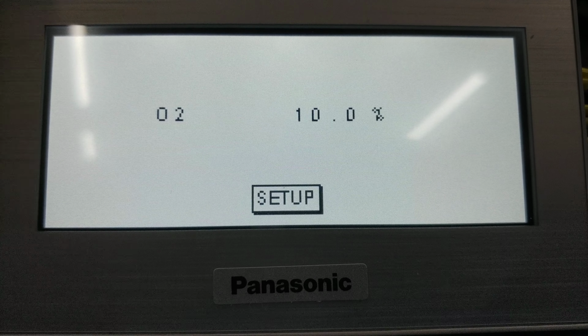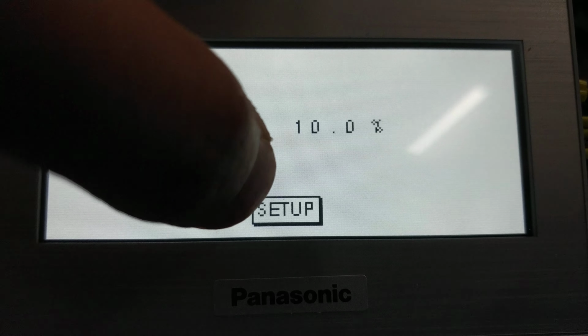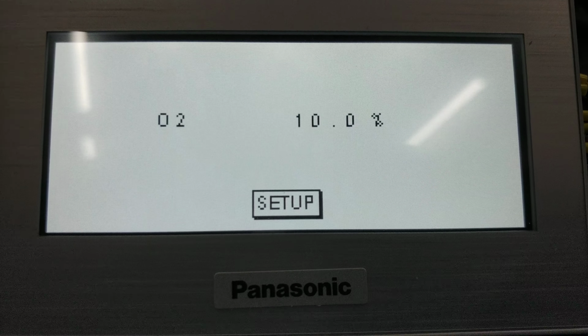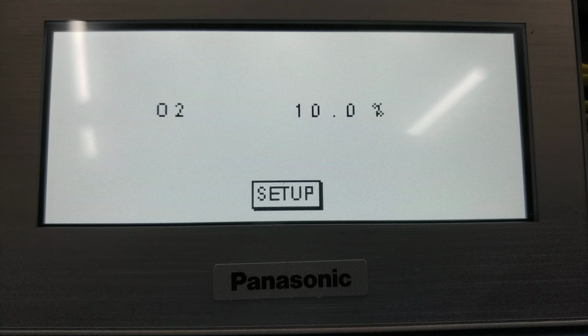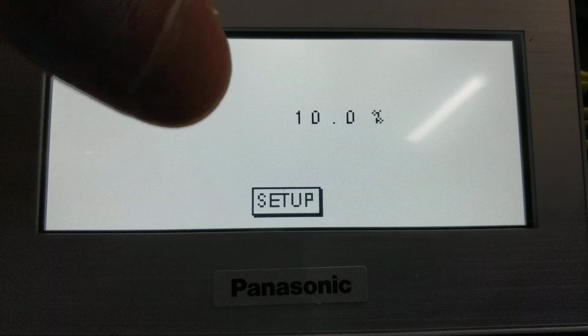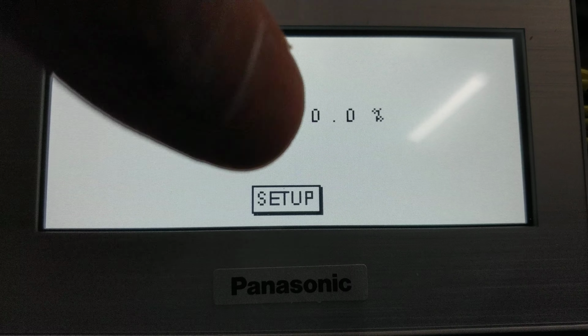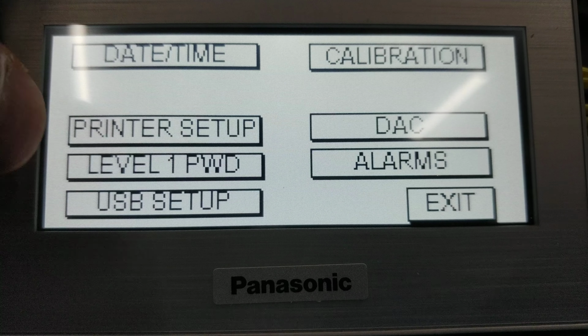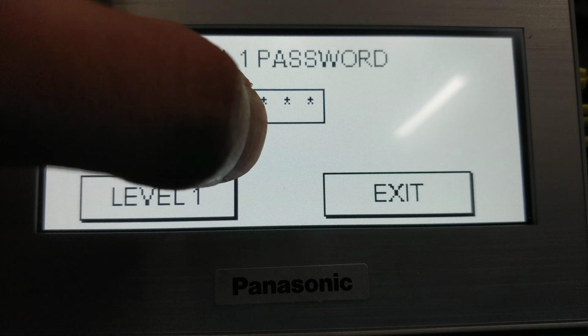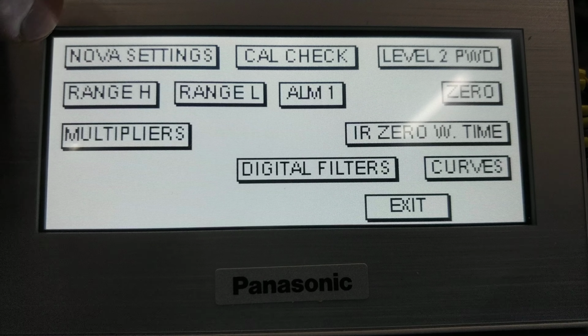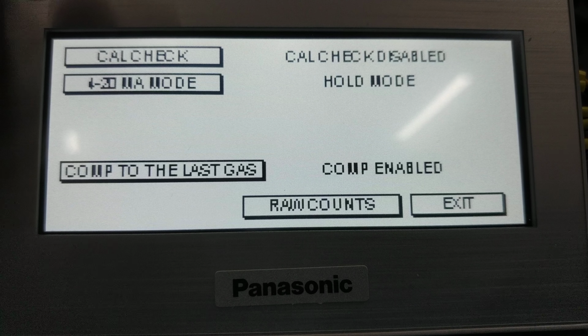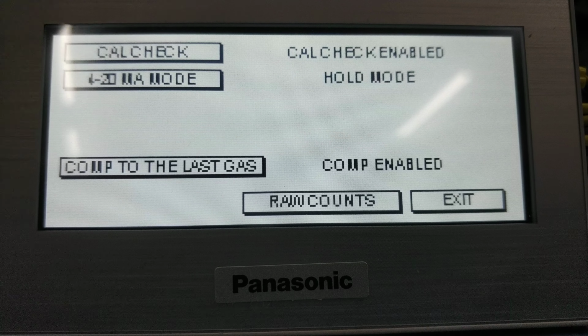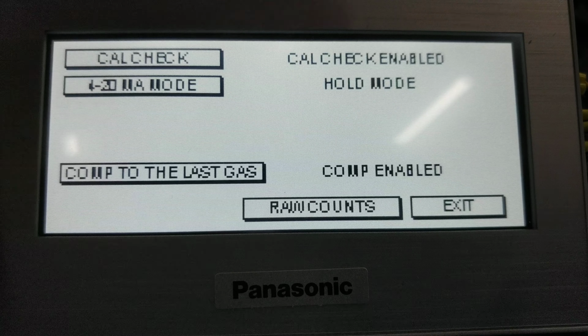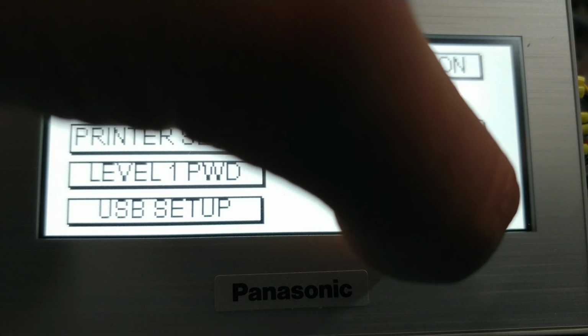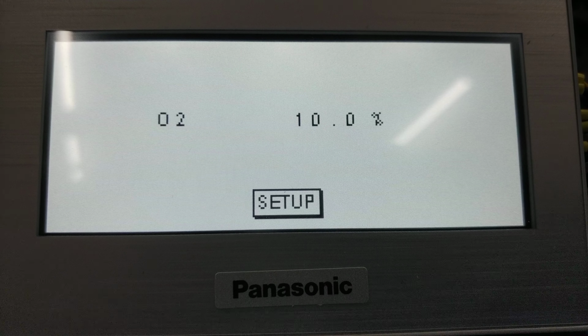Another thing we want to do is re-enable cal check for all future calibrations. The cal check is just a safety measure, to make sure you do not use erroneous calibration values whenever you're doing a calibration. So in this case, we're going to go back and re-enable cal check. So I'm going to go setup, level 1 password to level 1, 270, level 1, Nova settings, and I want to put that back to enabled. Cal check enabled. Once you do that, you're done, and you should be good to go. So exit, exit, exit. And that's how you do a calibration.